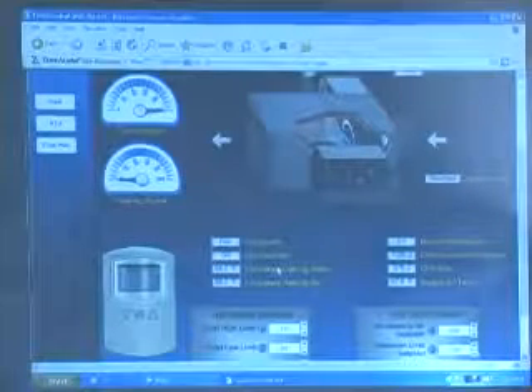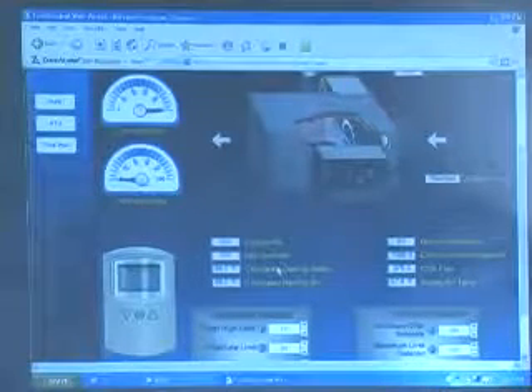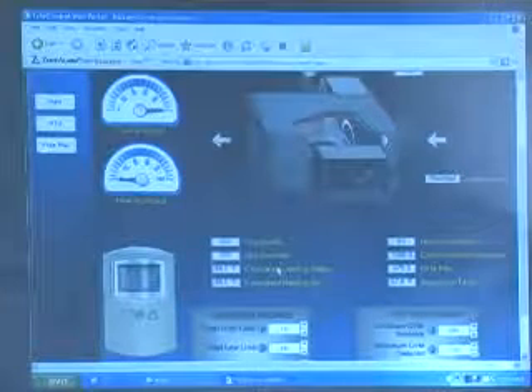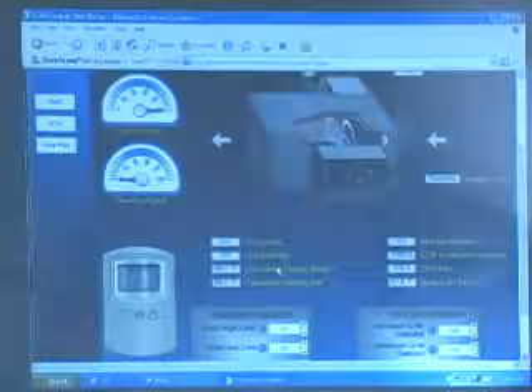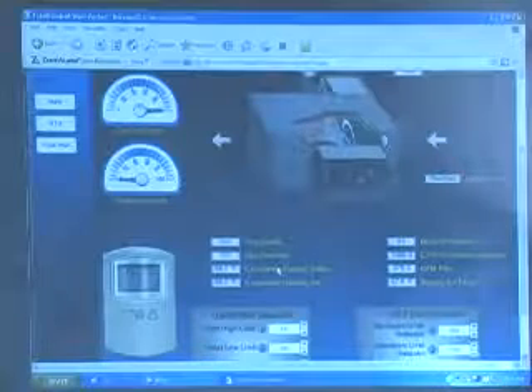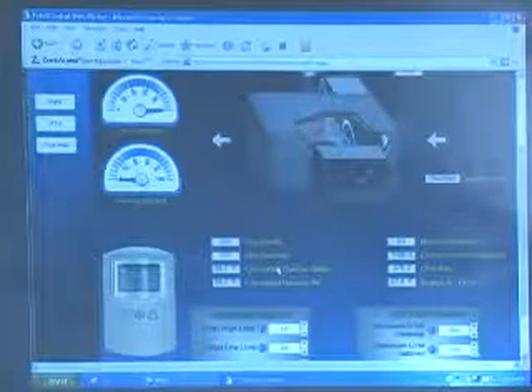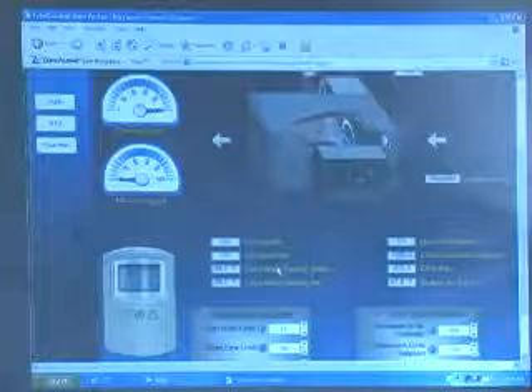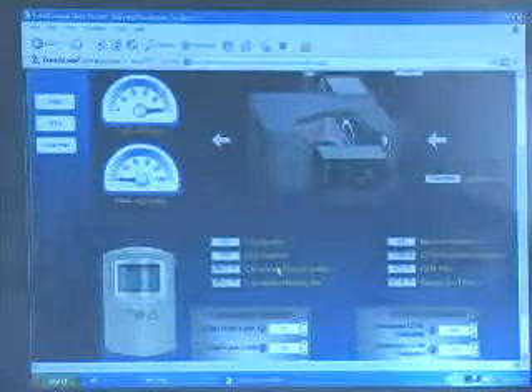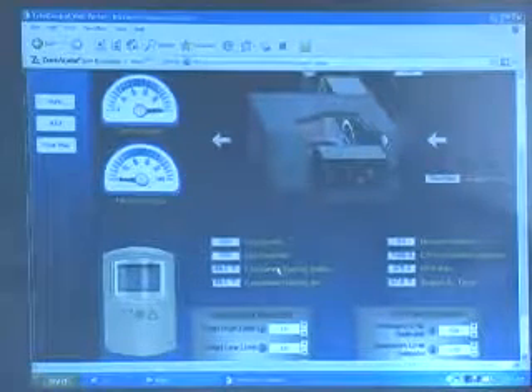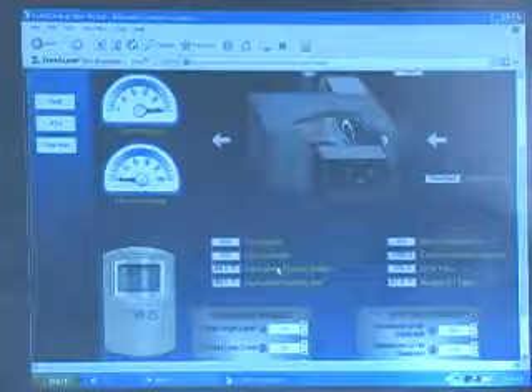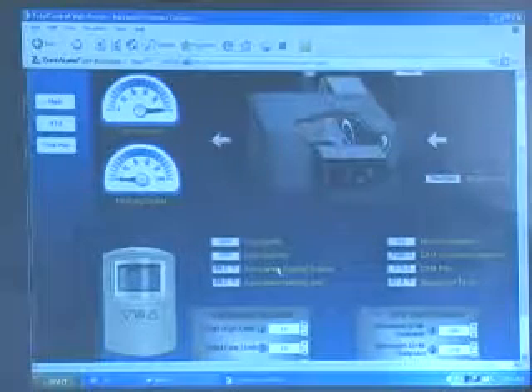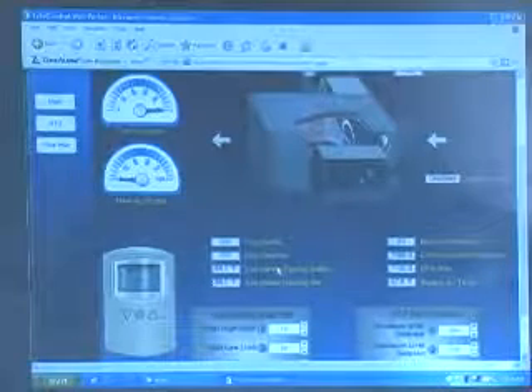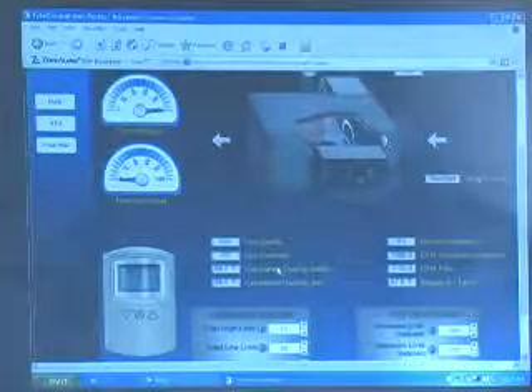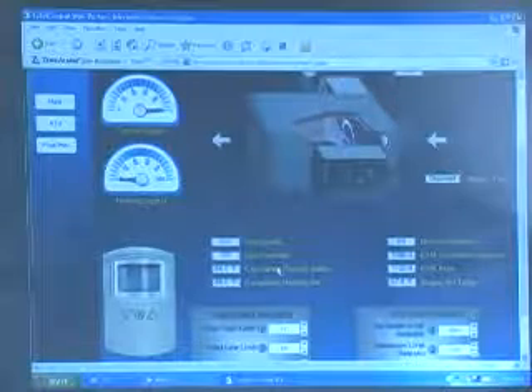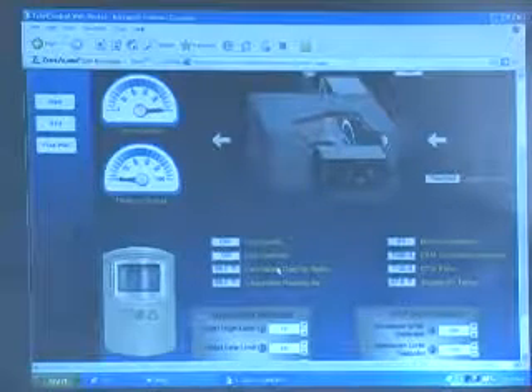For most every heating and cooling application, you have a cooling set point and a heating set point. We obviously don't want those to overlap, otherwise any potential energy savings are gone if you have heat and cooling on at the same time. So we have our own internal standards, and I'm sure most building automation contractors are the same. We usually offer a 2-degree deadband between heating and cooling. That's widely accepted for most applications, offices, schools. That's widely accepted as a standard starting point.